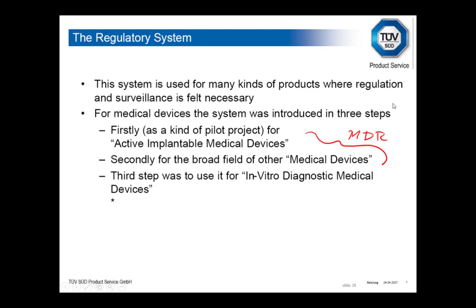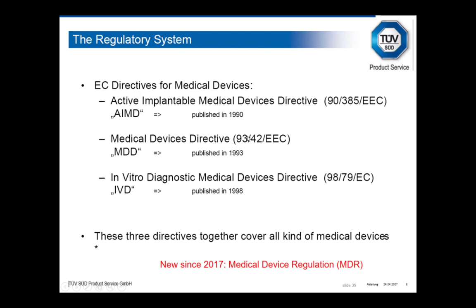Just to give you an idea how to read them, if you look them up on the internet, you always find the first number, that's the year, so 1990. Then there's a second number, that's this directive here has been number 385 in the year 1990. And then there's here EEC. In older times, it was the European Economic Commission. Then it was the European Commission. So it just means it's released by the European Union. I would kindly ask you also to have the true name in mind, because it's easier if you say the medical device directive, people know what you're talking about. If you talk about the 93/42/EEC, probably only 10% know what you're talking about, right?